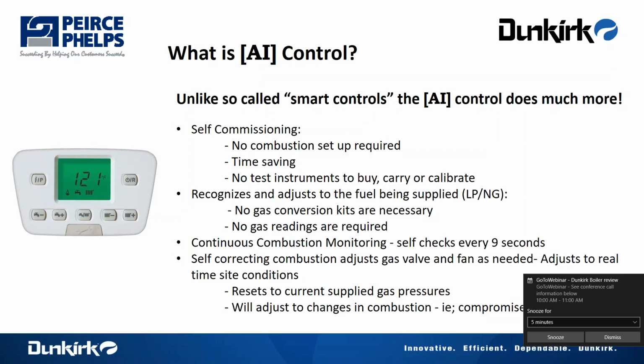You'll hit confirm, yes, and the boiler will go into standby mode. Beyond that, it's going to continuously monitor itself every 9 seconds, and it will self-correct as things change through the course of the heating season, through the course of the boiler's life. It's going to adjust to low gas pressure. That happens at cold periods of time. You're going to get varying gas pressures in different areas.